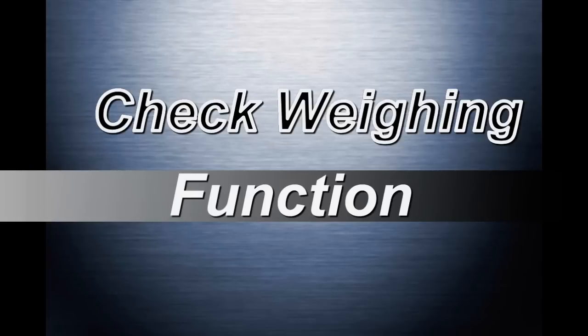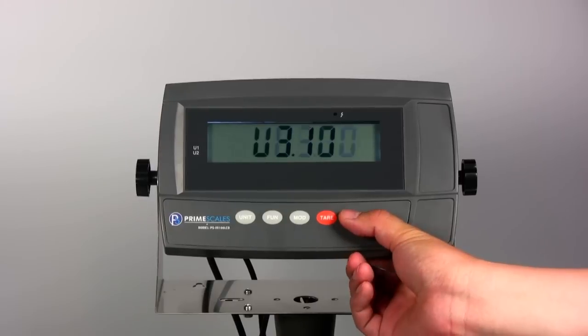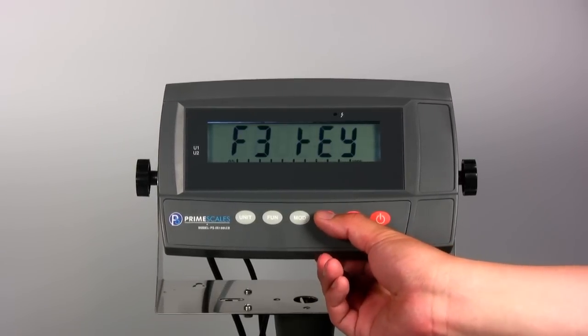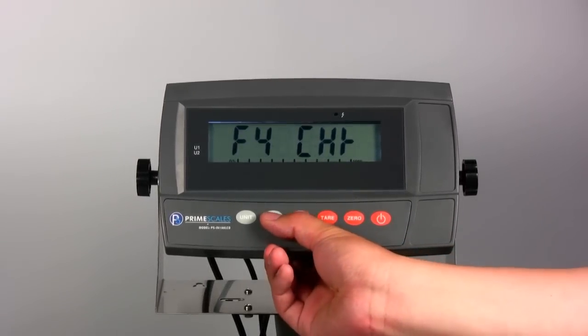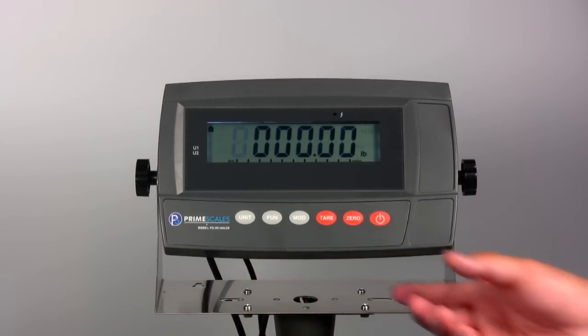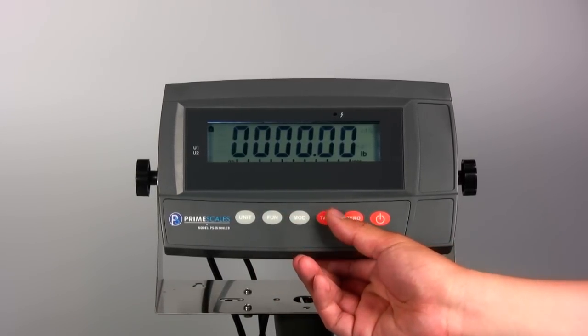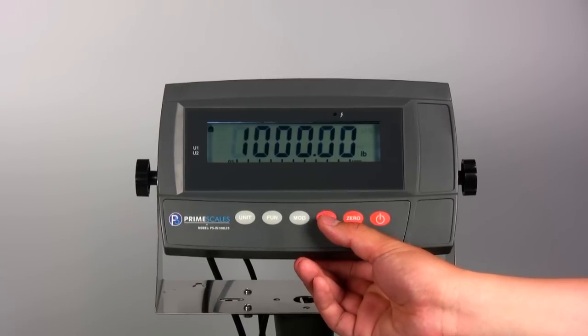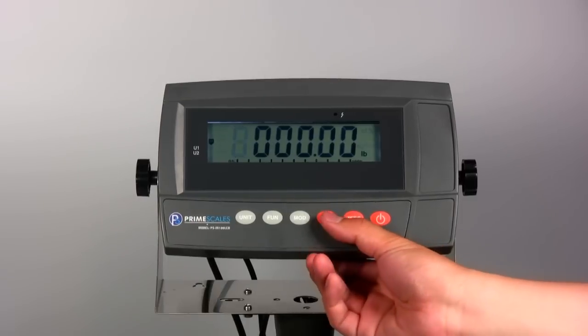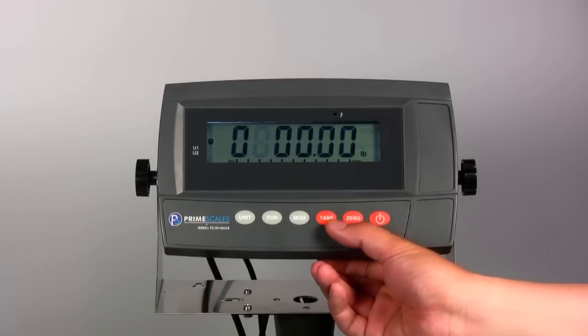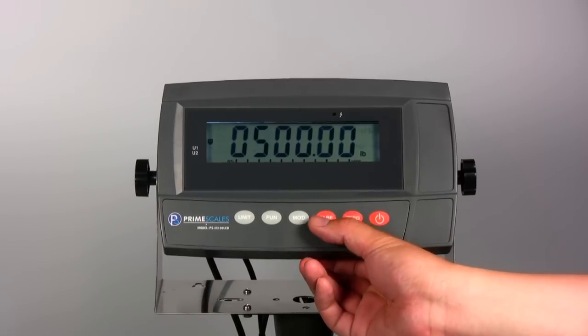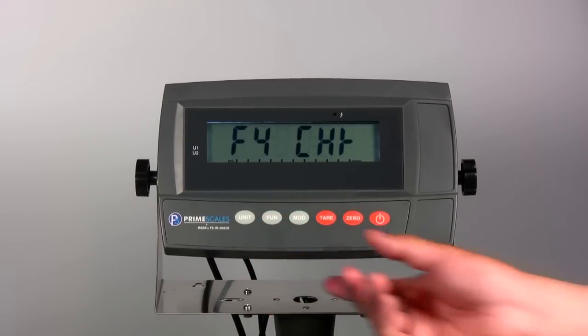Check Weighing is widely used in quality control. The indicator will show a sign and send a beep sound when the loaded weight is within or beyond the preset range. In the Check Weighing mode, first you need to preset the high limit and the low limit. Then select the beep sound mode. You can choose no sound, beep within the range, or beep beyond the range.